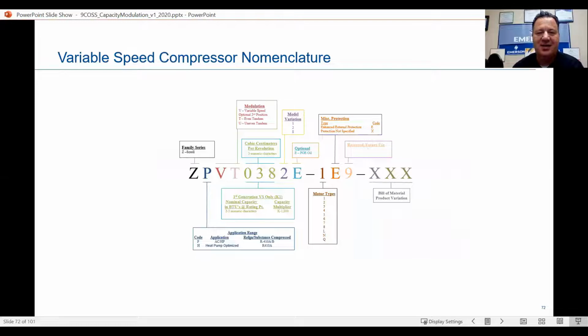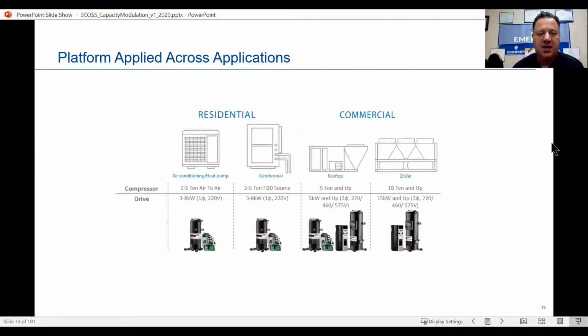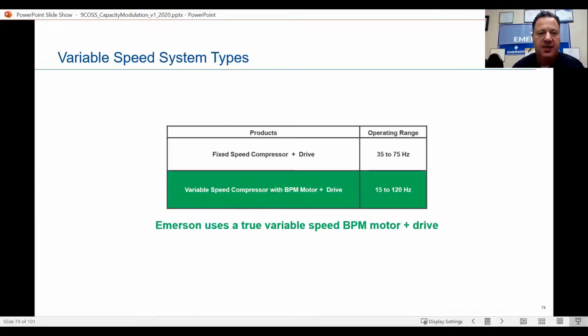Variable speed compressors, not going to hit this nomenclature too much. You all know how to read nomenclatures. The Z obviously is our scroll compressor. You can look at this on your own, but it just goes through and tells you what these mean. The V is a modulation. Some of the platforms applied to, obviously we have the drive. We can add to residential, geothermal, rooftop units, or chillers. On the commercial side, variable speed system types, products, fixed speed compressor plus a drive. Operating range on that is 35 to 75 hertz. Remember, we're really manipulating that hertz and converting that, and that's what's causing that speed to go up and down.